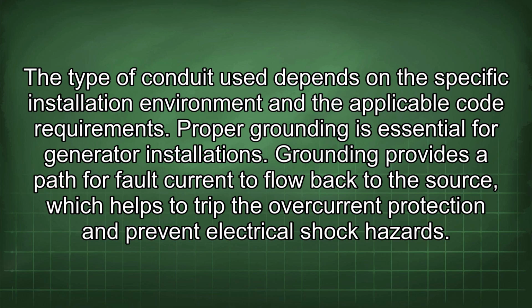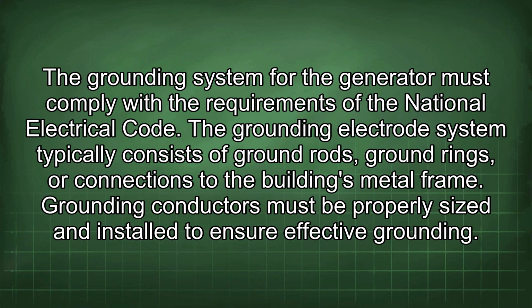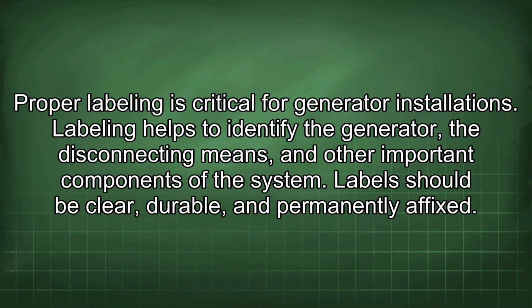Proper grounding is essential for generator installation. Grounding provides a path for fault current to flow back to the source, which helps to trip the overcurrent protection and prevent electrical shock hazards. The grounding system for the generator must comply with the requirements of the National Electrical Code. The grounding electrode system typically consists of ground rods, ground rings, or connections to the building's metal frame. Grounding conductors must be properly sized and installed to ensure effective grounding. Proper labeling is critical for generator installations.